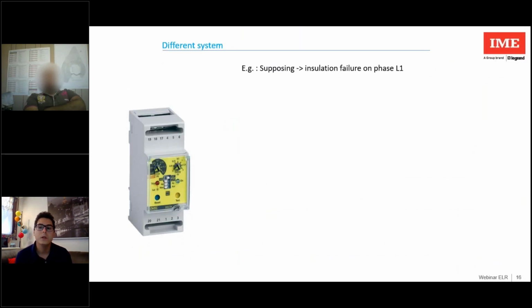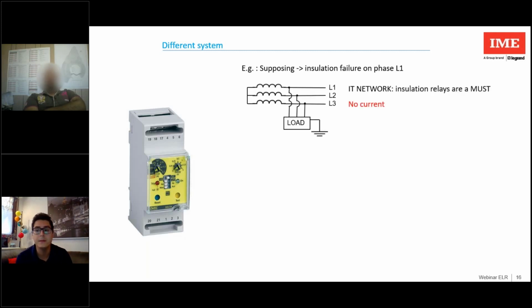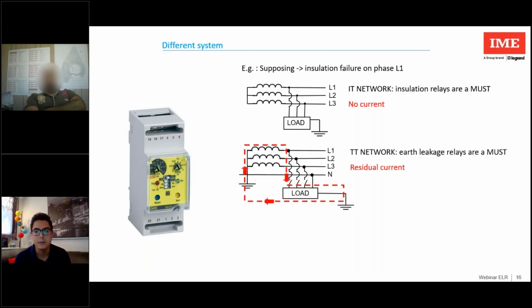Supposing we have an insulation failure on phase 1. In the IT system, the earth fault current returns to the power node through the earth system at the masses and the capacities to the earth of the line conductor. For this reason, a simple insulation monitor is a must. In the TT system, the earth fault current returns to the power node through the ground. Here, the ELR is essential.